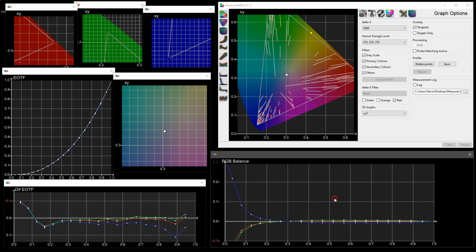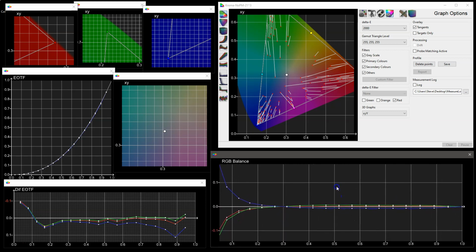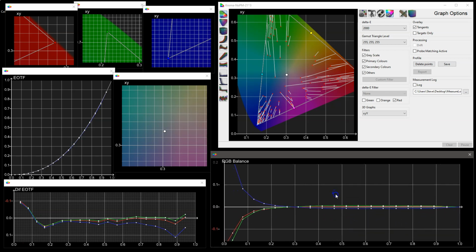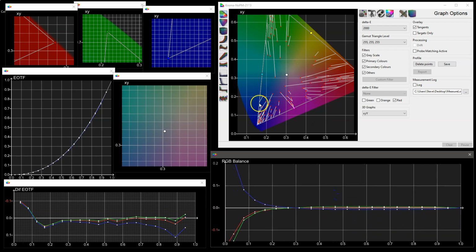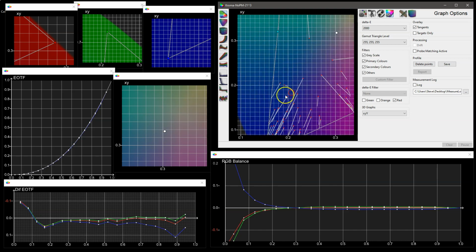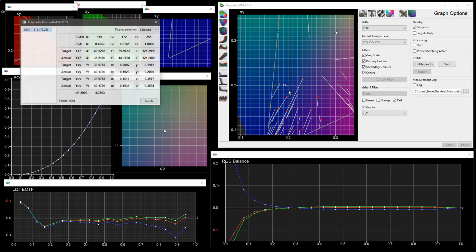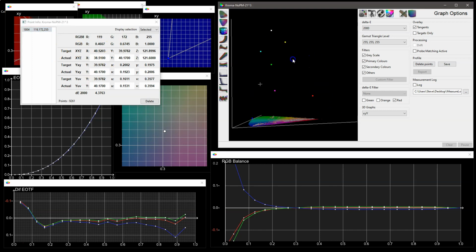So, knowing that, we can actually use the information provided in the tangent lines to see that that point there is tracking differently. That suggests that that's the error point we can see in the volumetric graph. If I double click it, we get some information on it, but more importantly, back in the volumetric graph, we now have a cross on that error. So that means that, yeah, that is the point that appears to have been read incorrectly.